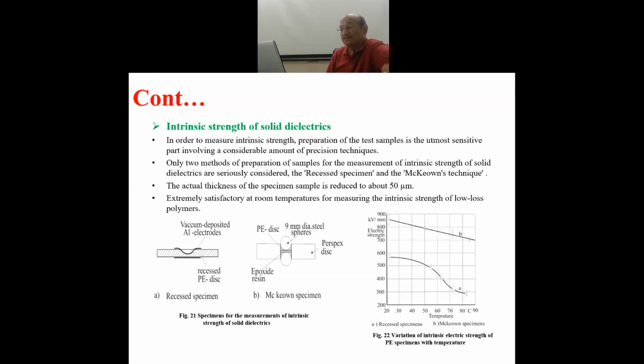And the other specimen sample was prepared by McKeown, and he prepared the sample in a slightly different way. It is given on the right side. He has taken a polyethylene disc. He's measuring the breakdown strength of polyethylene sheet of micrometer thickness, and it is placed between two perspex discs, and on both sides are 9 mm diameter steel spheres, very smooth steel spheres, very small.